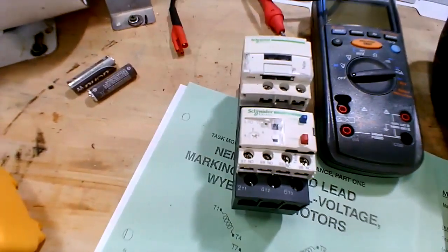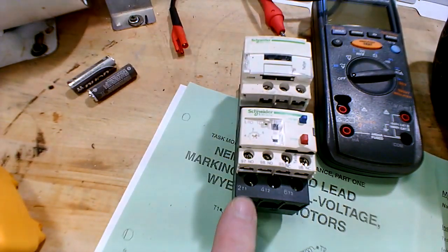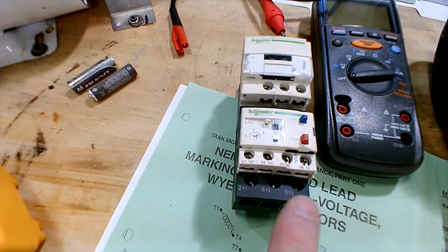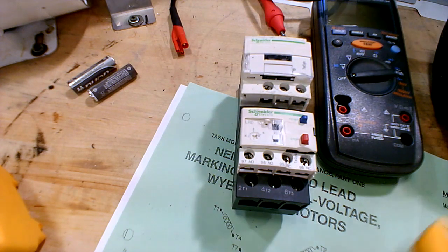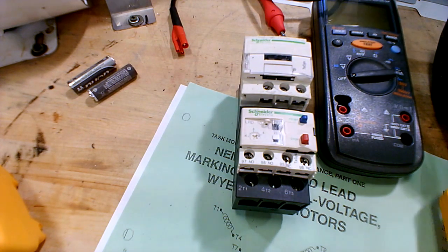Now listen real good here. Let's say, for instance, you got that motor ain't acting right, okay? And you check each one of these legs here to ground, check the voltage. And you get the proper voltage to ground, okay? So they're balanced. But yet when you check the amps, they're not balanced.